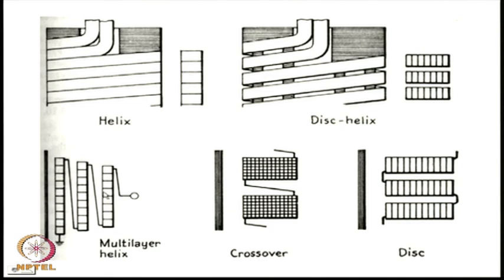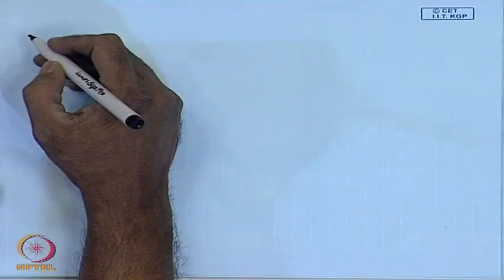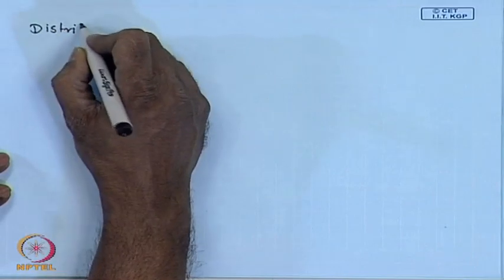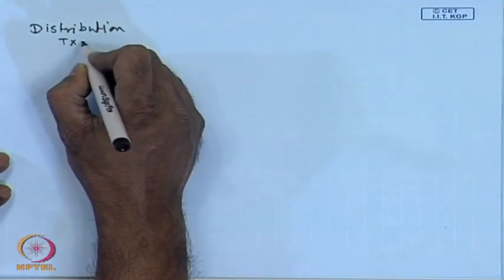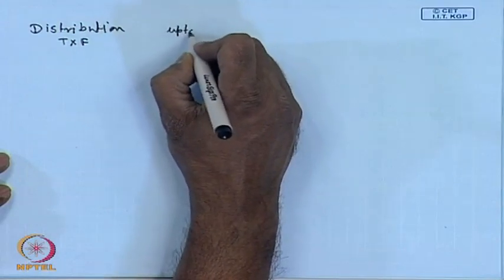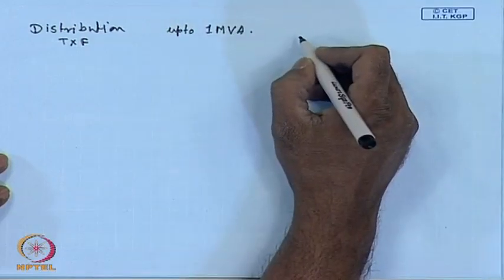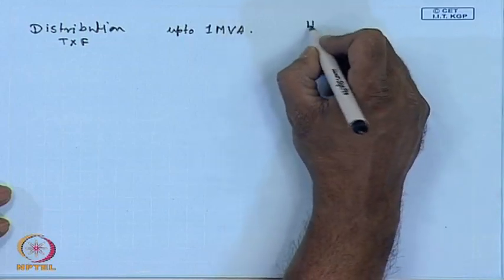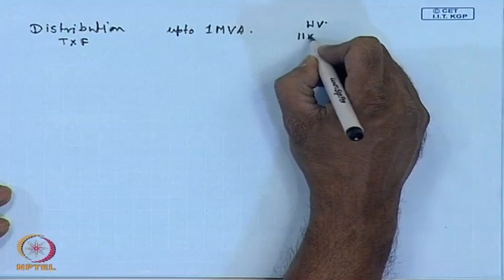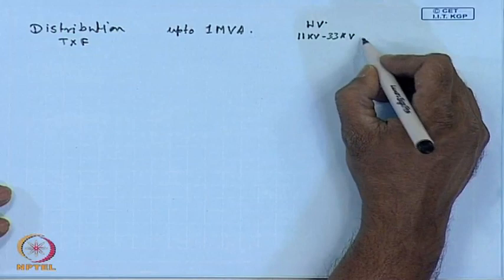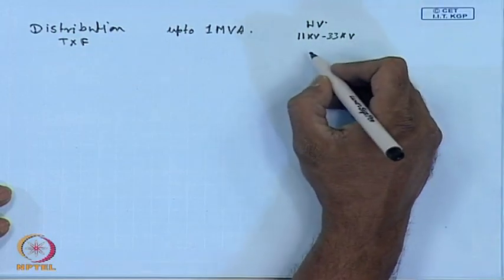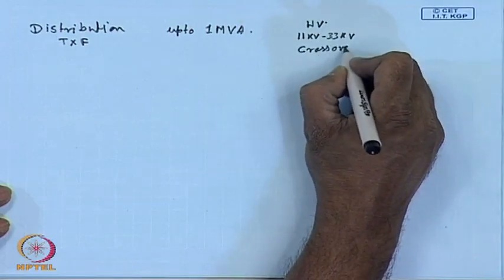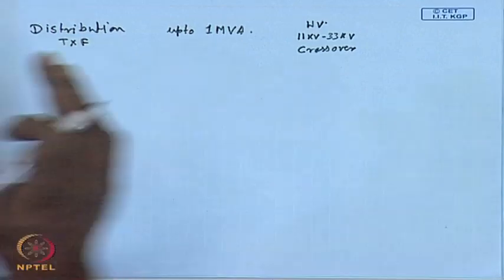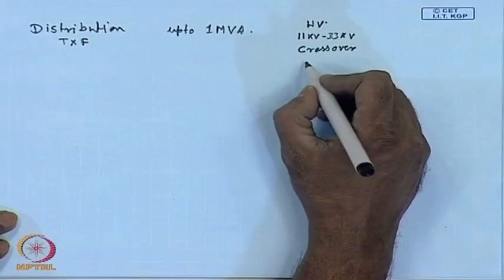Now, depending on the application, MVA rating and the kVA rating of the transformer in question, different windings are used. For example, if it is a distribution transformer, MVA rating, let us say up to 1 MVA, the HV voltage rating is 11 kV to 33 kV. Then the HV winding will normally be either crossover, this is the crossover winding, or multi-layer helix.